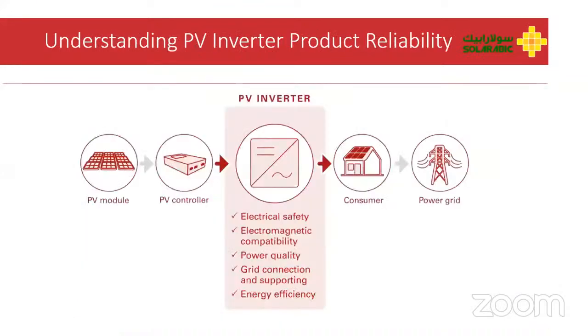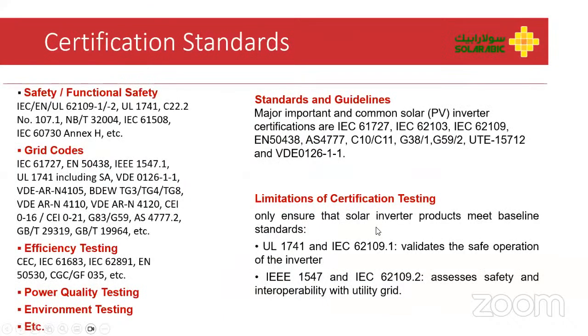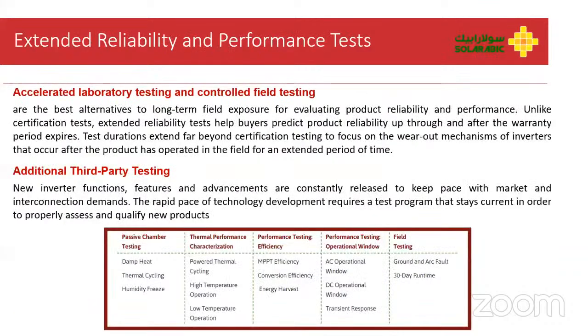So now, jumping into understanding the PV inverter product reliability itself, we have to study the electrical safety, electromagnetic compatibility, the power quality, the grid connection and support, and the energy efficiency of the particular inverter itself. We all know that there are international certifications in order to judge the inverter's quality, for example for safety, the grid codes, and the efficiency testing. But we have a certain limitation with these certifications. These certifications only tell us about the safe operation of the inverter, and most of them assess the safety and interoperability with the grid. They do not cover the extended reliability and performance tests.